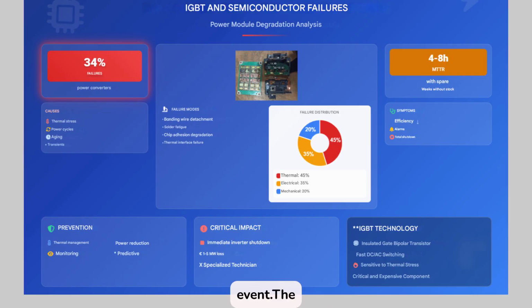The replacement cost of an industrial IGBT module can be between €2,000 and €5,000 per unit, plus the cost of specialized labor, urgent travel, and possible contractual penalties for unavailability. In scenarios without available spare parts, losses can multiply exponentially. Critical hours of solar irradiation between 11 a.m. and 5 p.m. are lost, directly affecting the project's monthly profitability and accumulating an unrecoverable opportunity cost.